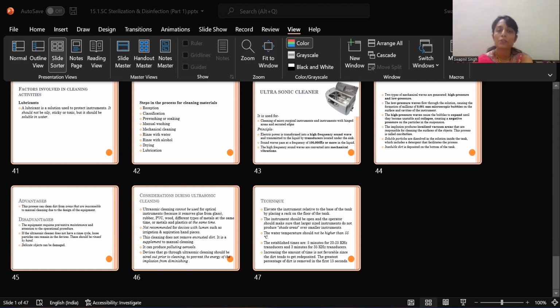The disinfectant concentration and contact time have to carry the same weight in contributing to the rate of inactivation. This disinfection activity can be expressed as the product of disinfectant concentration and contact time. The same values can achieve the same amount of inactivation. Now coming over to filtration.